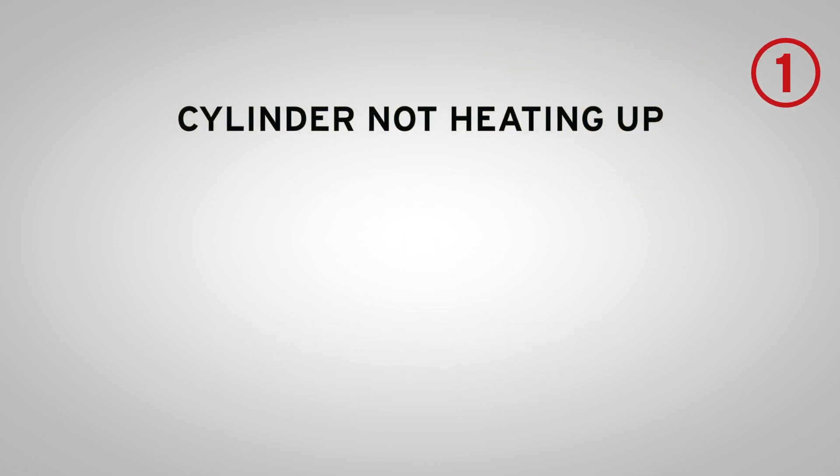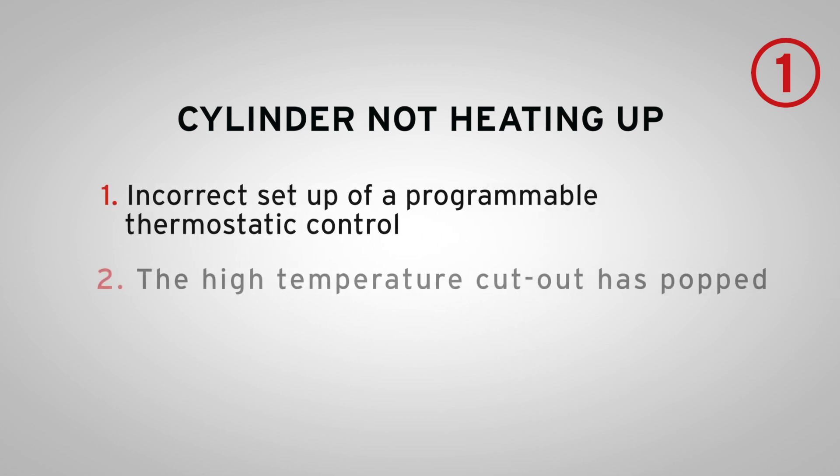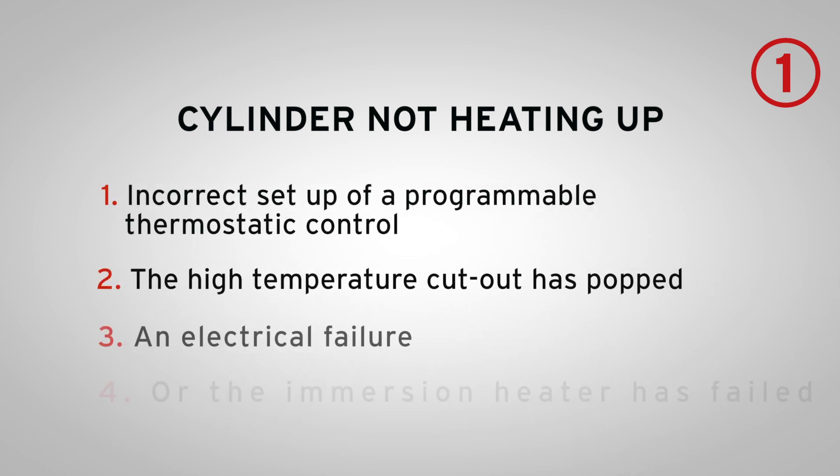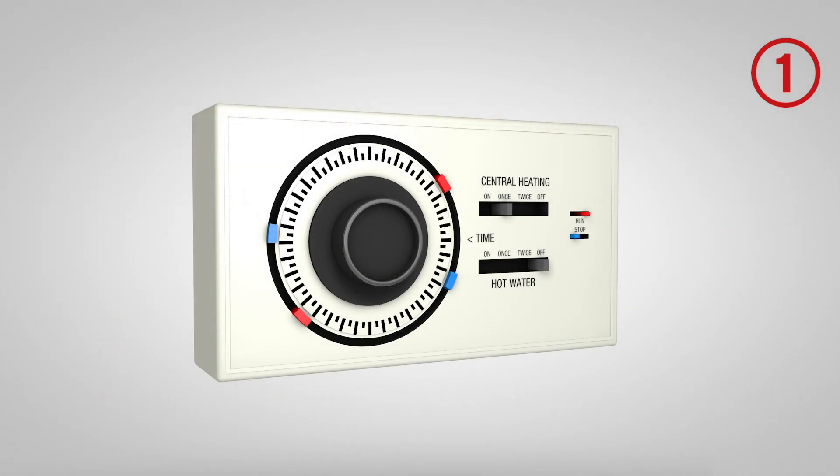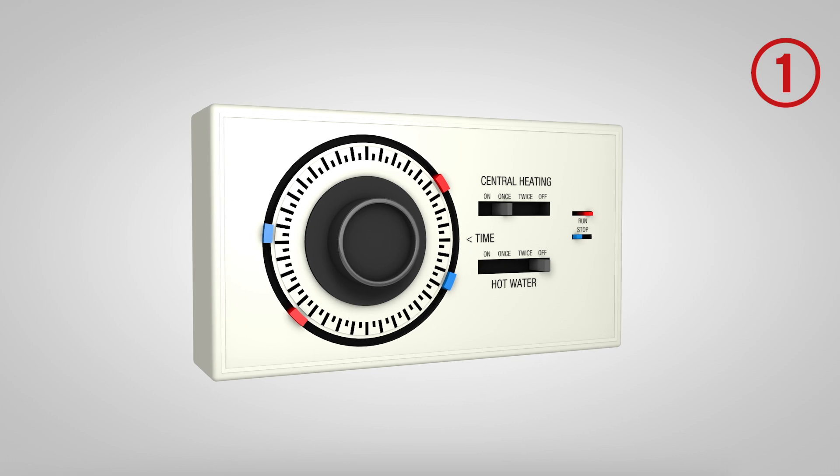Part 1. Cylinder not heating up. There are four possible causes that can prevent the water in the cylinder from heating up. These are: incorrect setup of a programmable thermostatic control, the high temperature cutout has popped, an electrical failure, or the immersion heater has failed. To meet building regulations on energy efficiency, modern controls are a lot more complex than the traditional on-off controls everyone is used to.